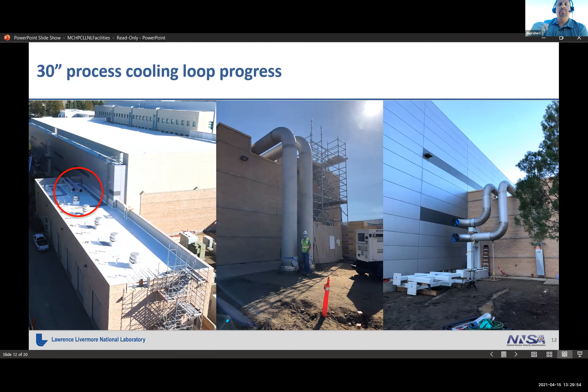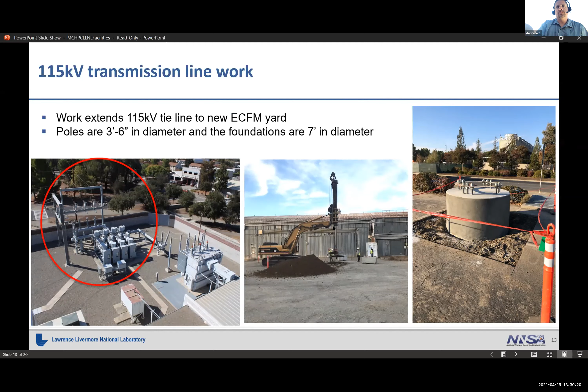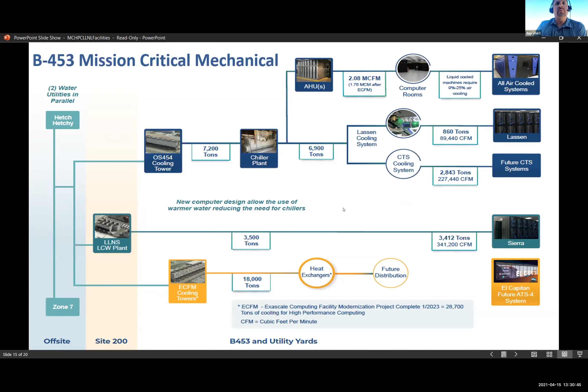We're bringing in a 115 kV line to the substation, which then would transform to 13.8 inside the building, and then to 2.5 megawatt transformers, and then again step down to 480 to feed our computers. Here's our electrical distribution, our mechanical distribution, where we will still have about 10,000 tons of chilled water and 18,000 tons of the new W3 water. We site several systems in our building, so we have a need for different temperatures.